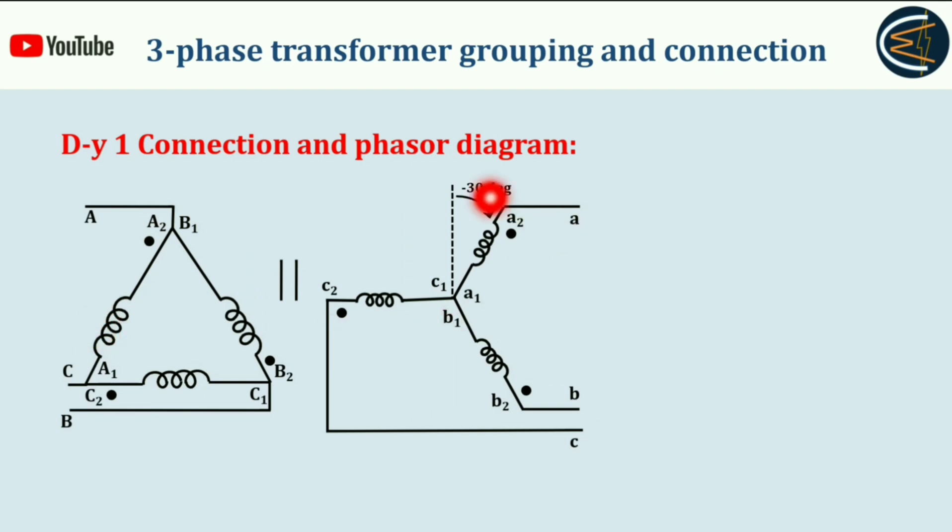side is delta connected, secondary side is star connected. As you can see here, there is minus 30 degree phase shift, or a clockwise phase shift, in order to make the individual phases parallel.